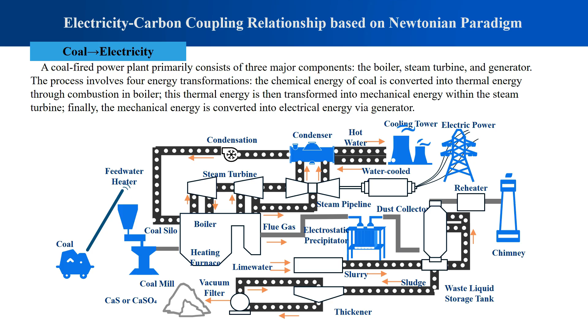The important engineering judgment is that power generation is not proportional to coal consumption through a universal constant. The coefficient depends on lower heating value, boiler thermal efficiency, pipeline efficiency, turbine internal efficiency, mechanical efficiency, and generator efficiency. The same coal flow can produce different electrical output if the unit operates at different efficiency.